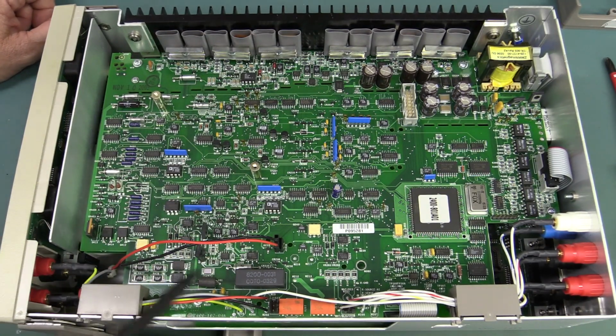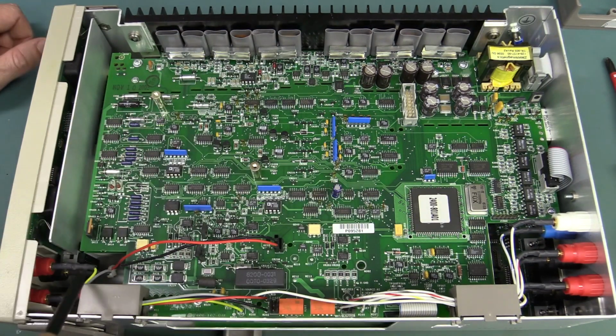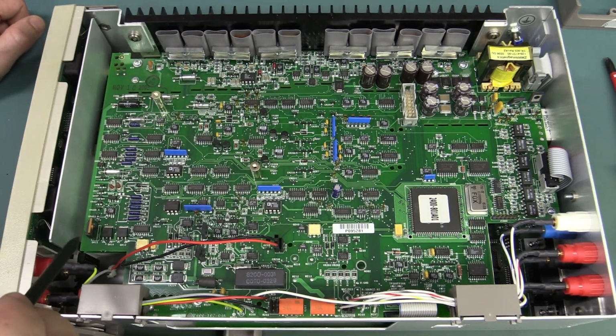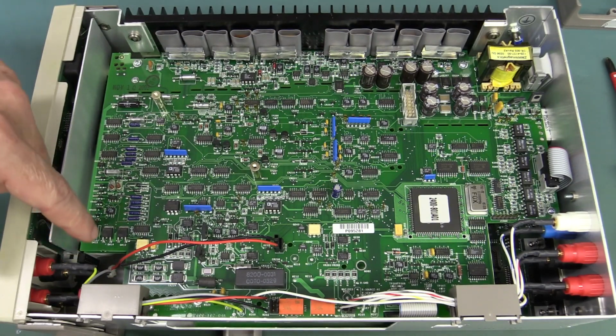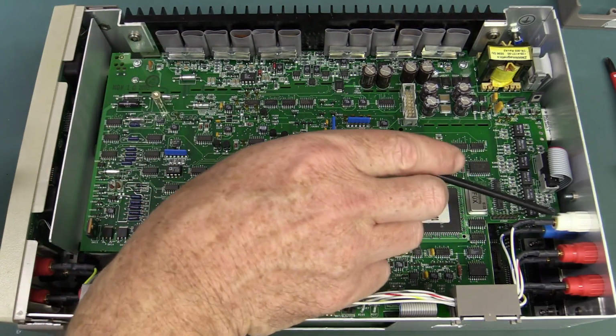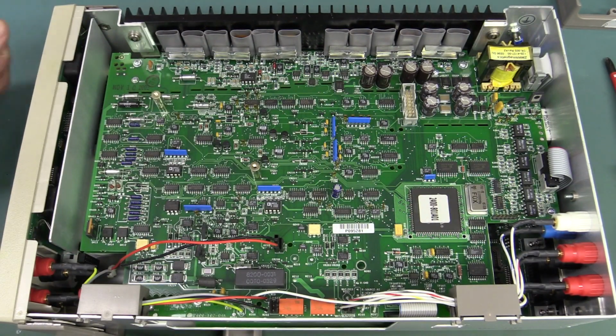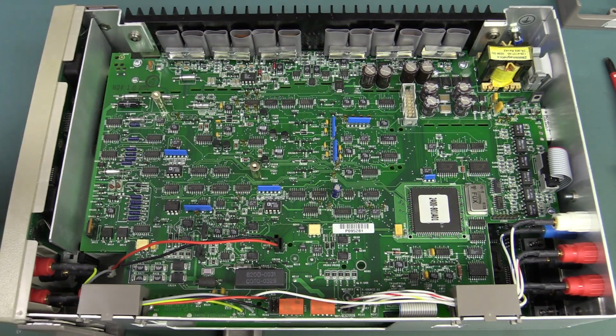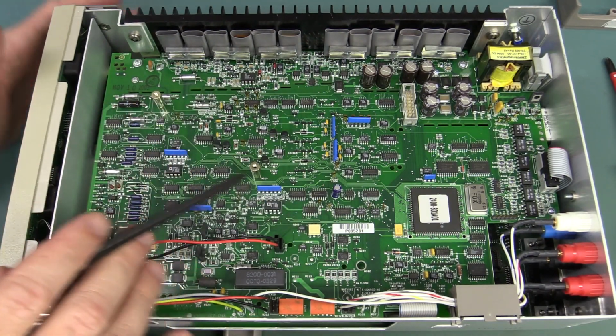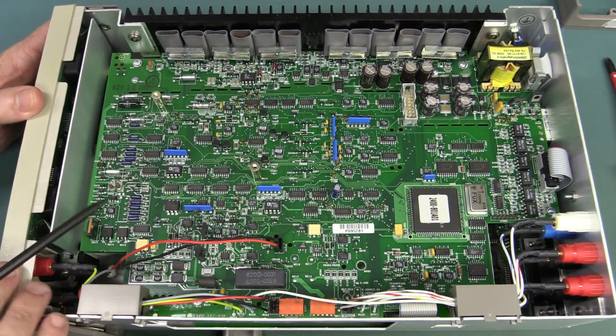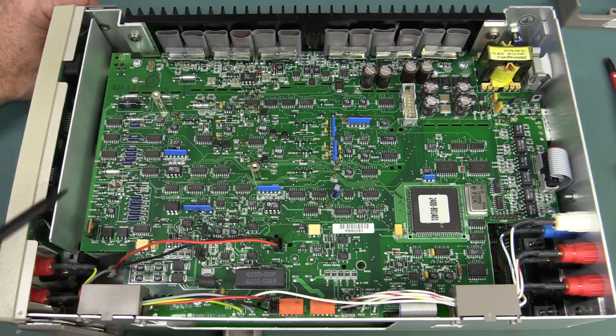The reason I say that is because, look, here are the front panel terminals over here. These will no doubt be low thermal tellurium copper contacts, same with the ones at the back as well. Spared no expense on the terminals, because this thing has a full-scale current range of 1 microamp, and 5.5 digits resolution on that. So I think it goes down to 10 picoamps or something like that resolution. So we're talking very low current in here. Not as low as the new model, by the way. The 2450 goes an order or two lower than that, I think.